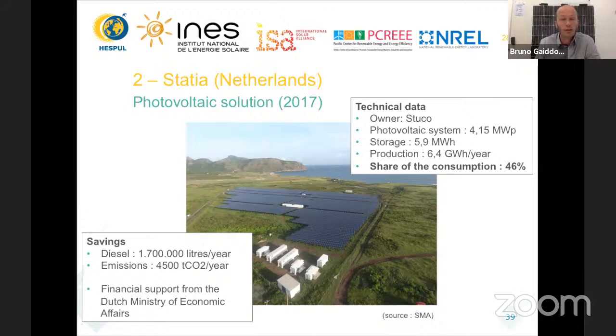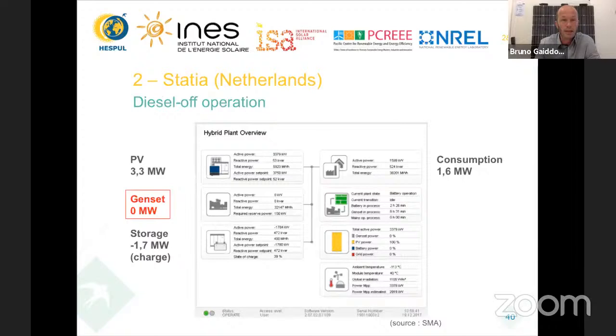What was demonstrated in this second case study is what we call diesel-off operation. The PV system is so large, and the storage has such an important capacity, that it's possible to switch off the diesel genset for several hours a day. Here is a screenshot of the utility's operating screen: the consumption of the island is 1.6 megawatts, while the PV produces twice as much, 3.3 megawatts.